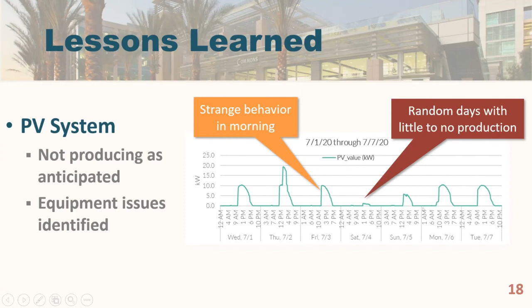So it's really critical. Even if your project adds PV but doesn't have enough money for end-use submetering, if you could only add one meter, I would add it on the PV. With the PV submeter and your net utility data, you can figure out your building consumption and your PV system production, and keep an eye on that PV system.